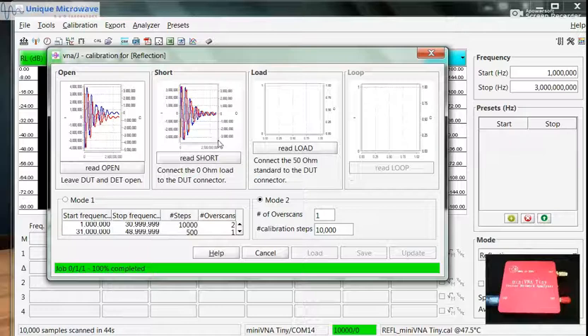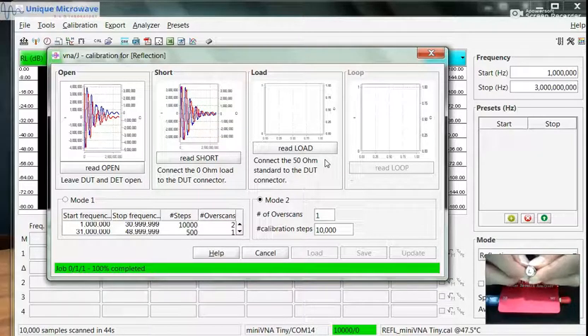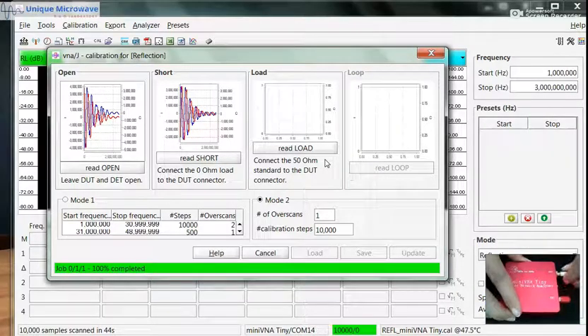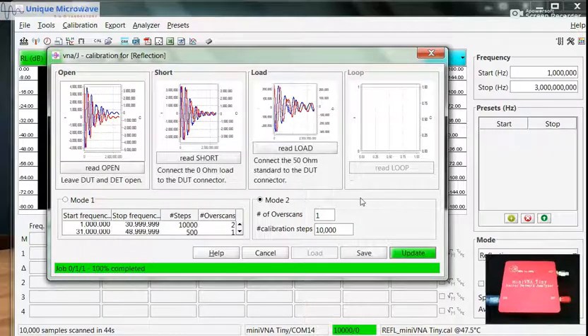Now we can replace it with the 50 ohm match load. Remove the short circuit from the DUT port and replace it with the 50 ohm match load. Then click Read Load. The one-port calibration is now completed.